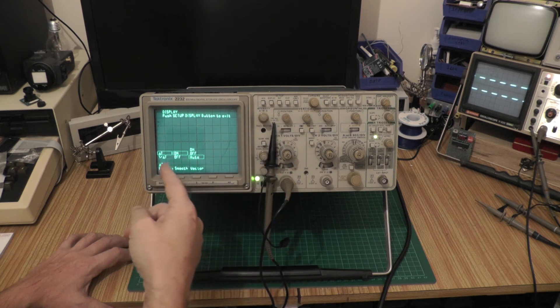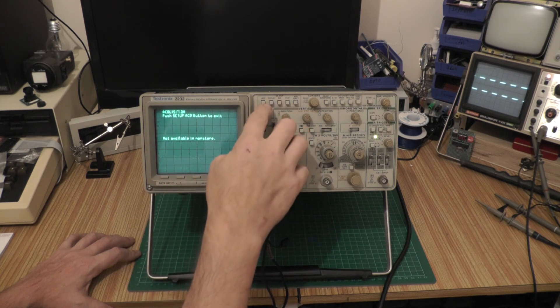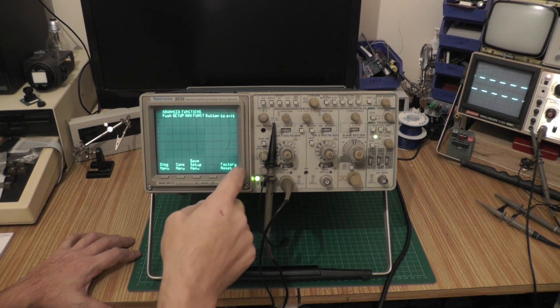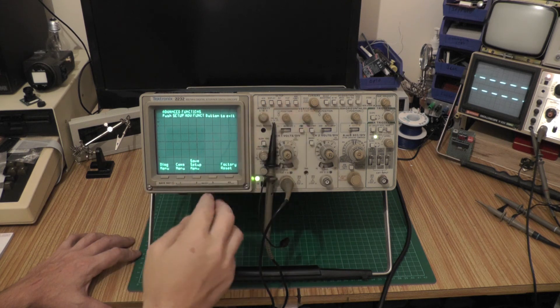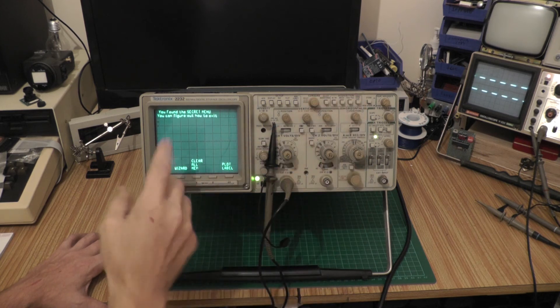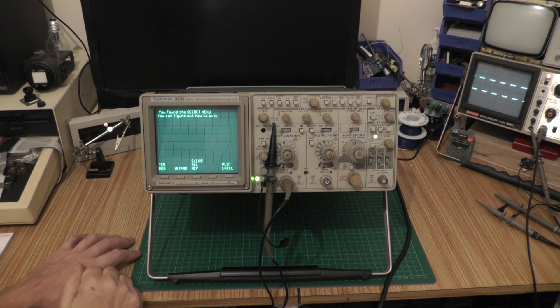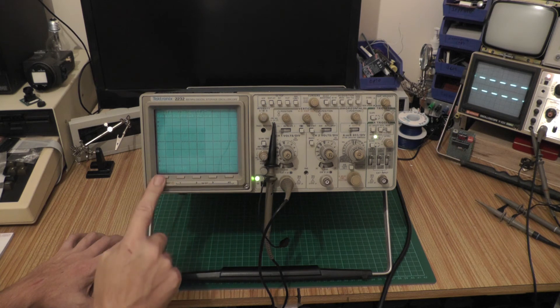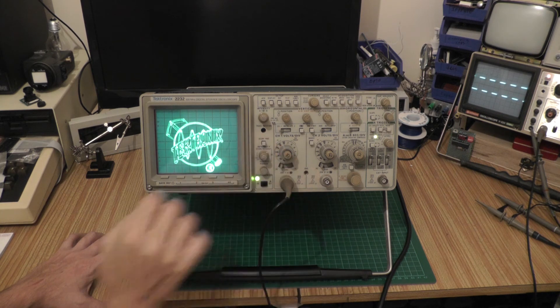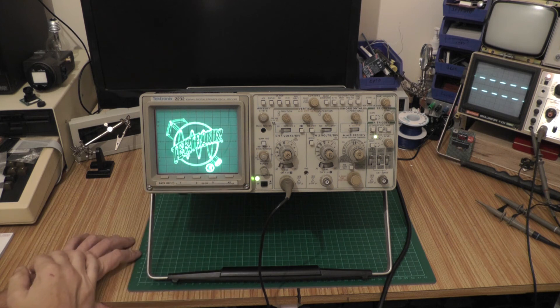There's a display setup where you can decide what's shown on screen, and an acquisition menu. Interestingly, in the advanced function menus there's a blank position number three — if you press the blank button twice and move the cursor knob, you get a secret menu, essentially an Easter egg. You can exit by pressing the advanced function menu button again. There's a TekBug and Wizard option — pressing TekBug gives you a nice vector display of the Tektronix logo on screen.